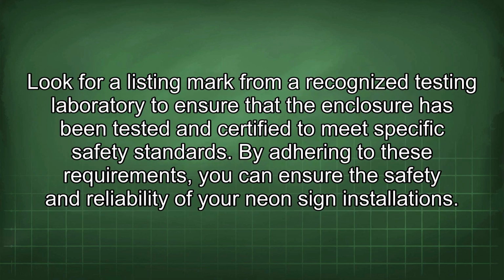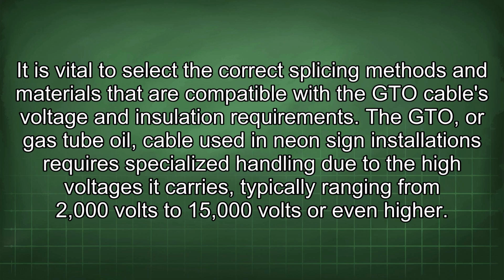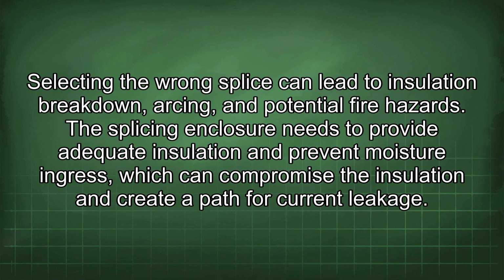Look for a listing mark from a recognized testing laboratory to ensure that the enclosure has been tested and certified to meet specific safety standards. By adhering to these requirements, you can ensure the safety and reliability of your neon sign installations. It is vital to select the correct splicing methods and materials that are compatible with the GTO cable's voltage and insulation requirements. The GTO, or gas tube oil, cable used in neon sign installations requires specialized handling due to the high voltages it carries, typically ranging from 2000 volts to 15,000 volts or even higher. Selecting the wrong splice can lead to insulation breakdown, arcing, and potential fire hazards.